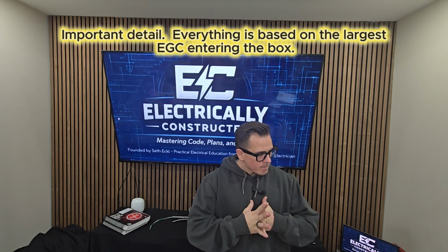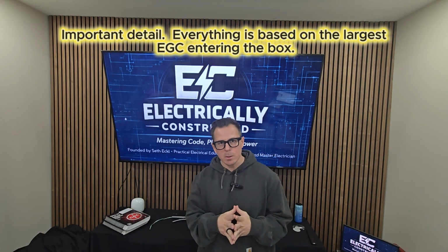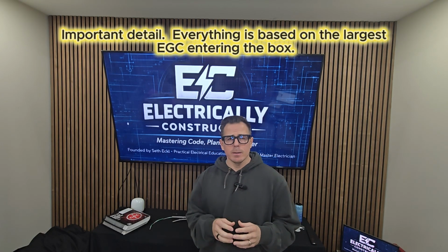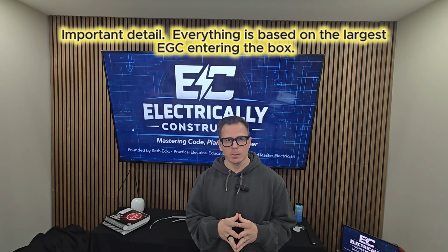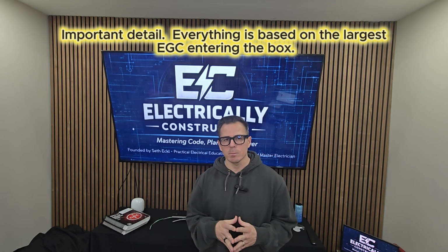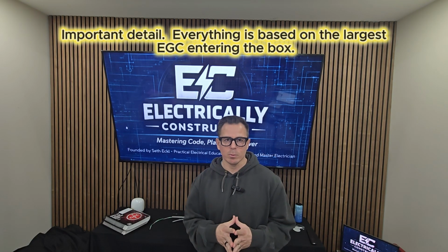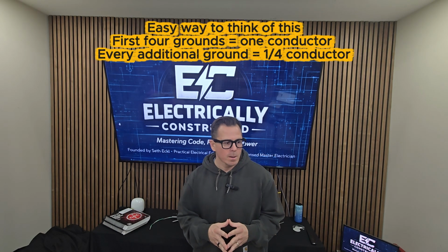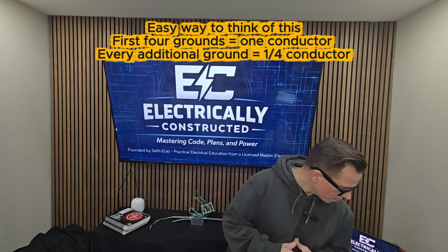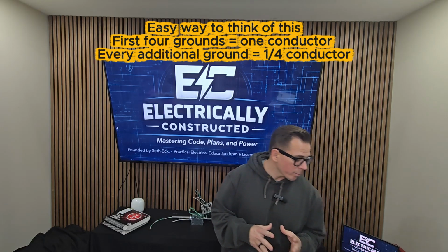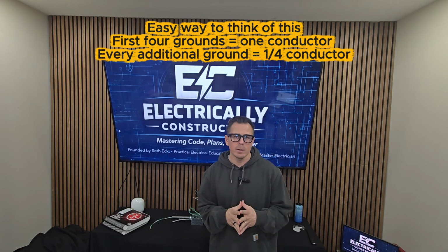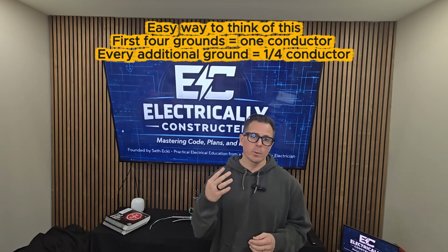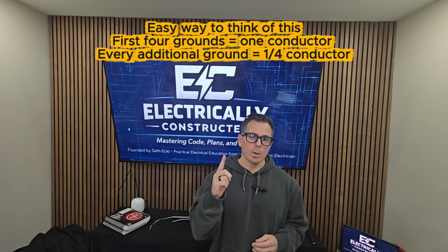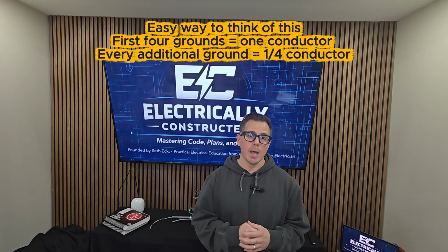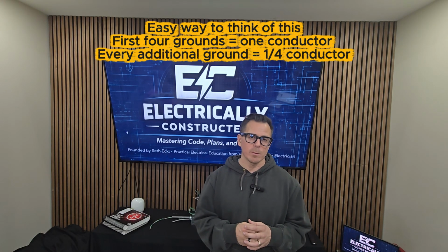I also want to mention that one of the important details of this rule is that it's the largest equipment grounding conductor in the box that the calculation is based on. So don't forget that. That's an important one. And another one I wanted to bring up was an easy way to remember equipment grounding conductor fill: the first 4 wires of equipment grounding are equal to 1 conductor. After that, you just add a quarter conductor. Try to keep it simple like that.